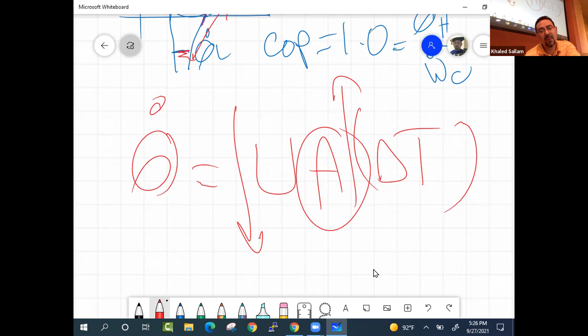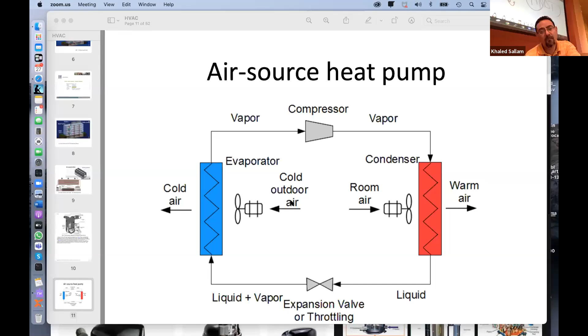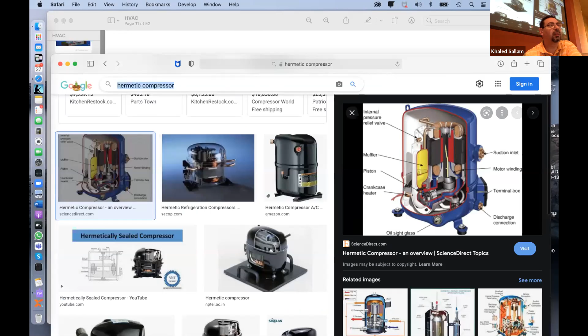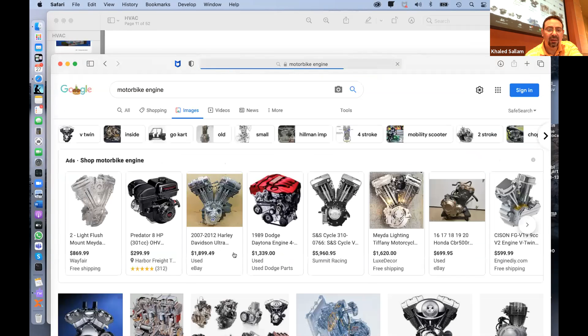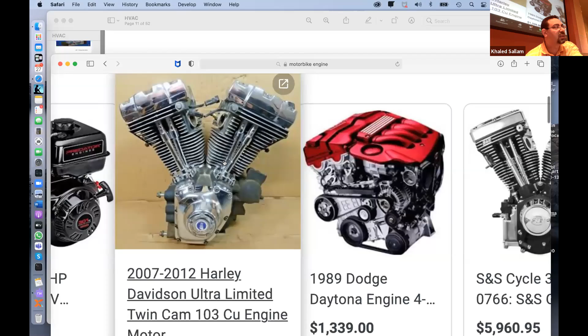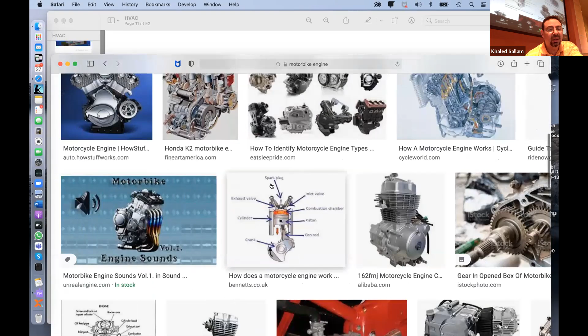Fins, right? If you look at any motorbike engine, you'll find tons of fins sitting on it. Why so many? Because they know if H isn't helping with cooling, they need a lot of area, so they make all those fins. You will never find fins on things cooled by water, because the H is big enough there, way bigger. So if a pipe has fins on the outside, you know it's air cooled. But if there are no fins, you know it's water to water, or refrigerant to water.